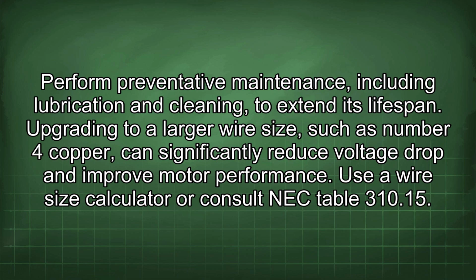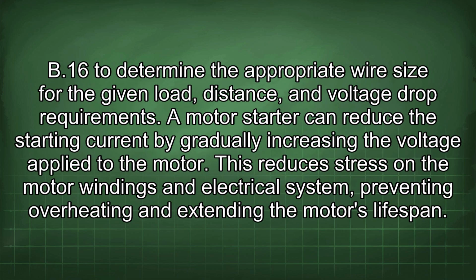Upgrading to a larger wire size, such as number 4 copper, can significantly reduce voltage drop and improve motor performance. Use a wire size calculator or consult NEC table 310.15(B)(16) to determine the appropriate wire size for the given load, distance, and voltage drop requirements.